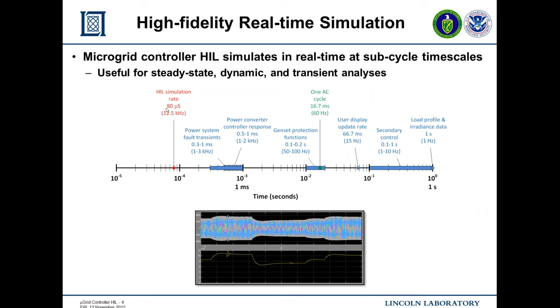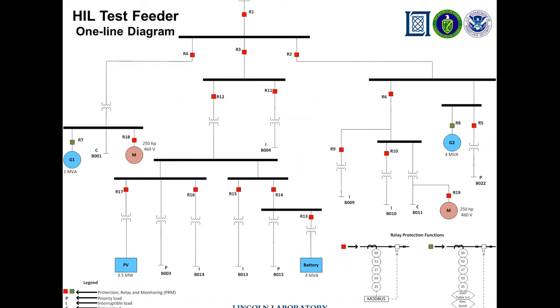For our simulation, we ran at a rate of 80 microseconds — well above the Nyquist frequency for fault transients and power controller response. We simulated an eight-megawatt microgrid based on real data, with real-time data at one-second intervals. The system includes a 1-MVA and 4-MVA genset, a 3.5-megawatt PV array, and a 4-MVA battery. We implemented realistic protection functions at various relay locations, as well as realistic models of lines, transformers, and loads.